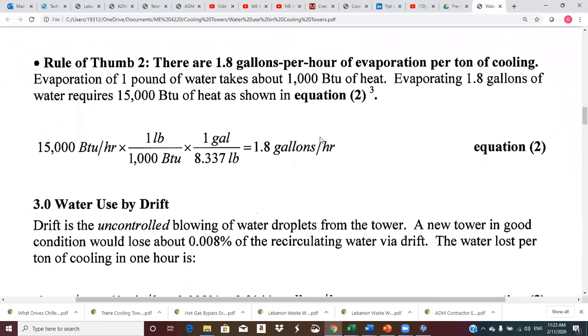Okay. Rule of thumb 2, 1.8 gallons per hour of evaporation per ton of cooling. 1.8 gallons per hour for every ton of cooling. So for evaporation, we use this nominal number here: evaporating or condensing a pound of steam or evaporating a pound of water is nominally 1,000 BTUs. If pressure goes up, this goes down some, but anyway, this all happens at atmospheric pressure. So that's pretty close. That's a good number.